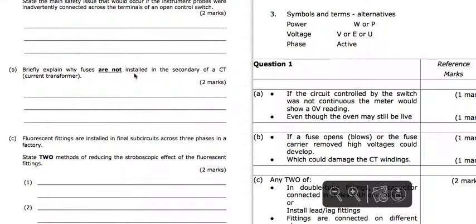Why is a fuse not installed in the secondary of a CT, a current transformer? Well, a current transformer is very dangerous if the secondary is open circuited, so it should always be connected. And so if we put a fuse in there and that fuse blows, then we could get dangerously high voltages across the CT windings.